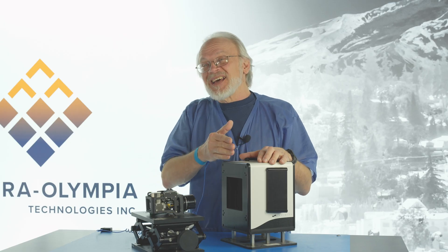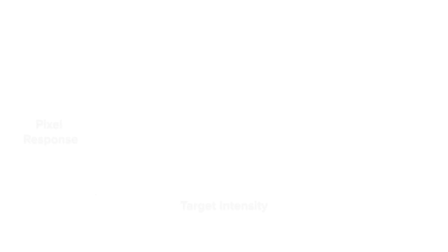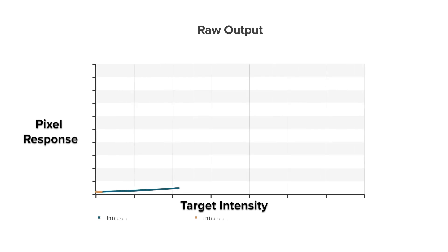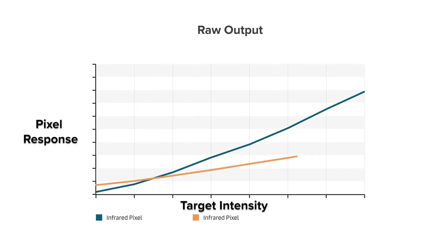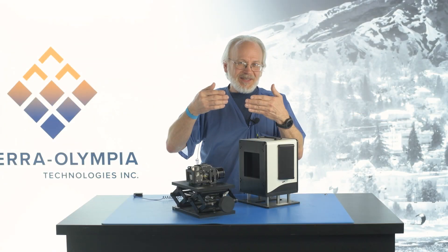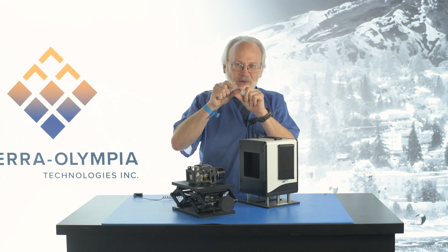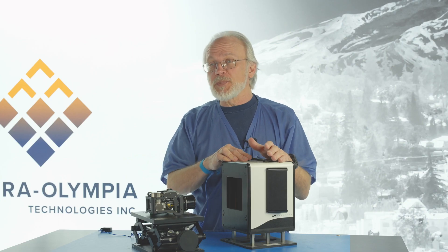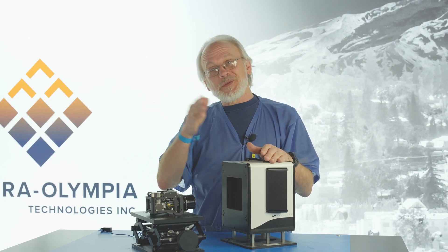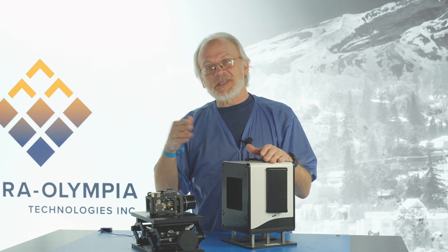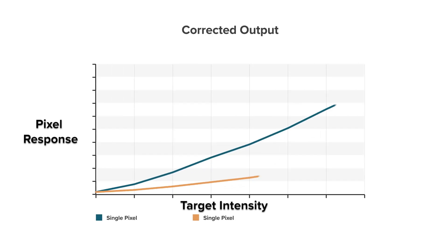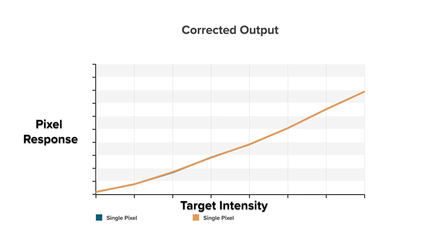If we do that on another pixel — say the adjacent pixel — we're going to find that it will have a slightly different characteristic. The reason this happens is because even if it's the same material on the same substrate, the way that we make detectors happens at a micro scale. We use an automated computer program to go through each of the 300,000 pixels in the array and alter each one individually so that the entire array becomes uniform.